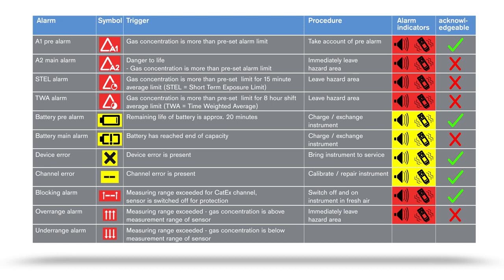If the measured value falls into the negative range, a so-called underrange alarm is triggered. This situation can occur, for example, if a fresh air calibration has been carried out in an area within which concentrations were already present. Please carry out a fresh air calibration in an area where fresh air prevails.